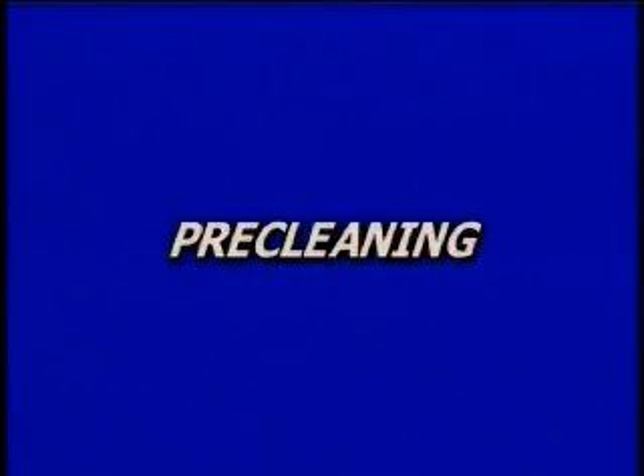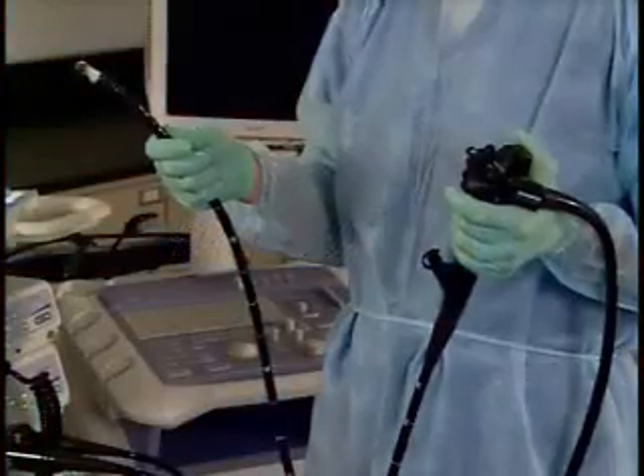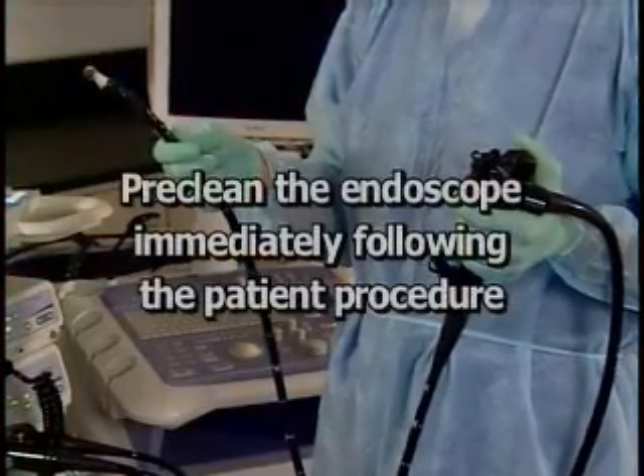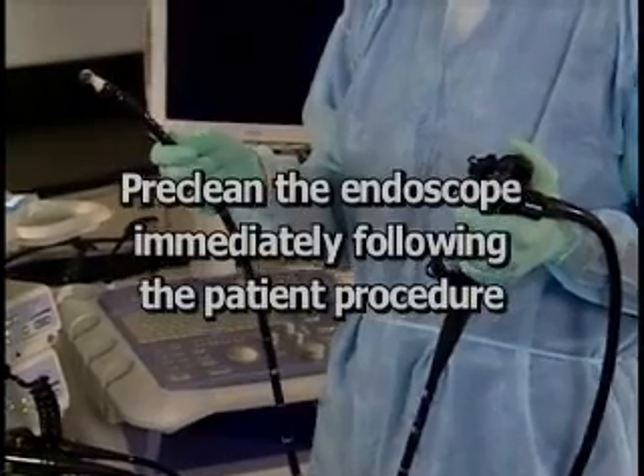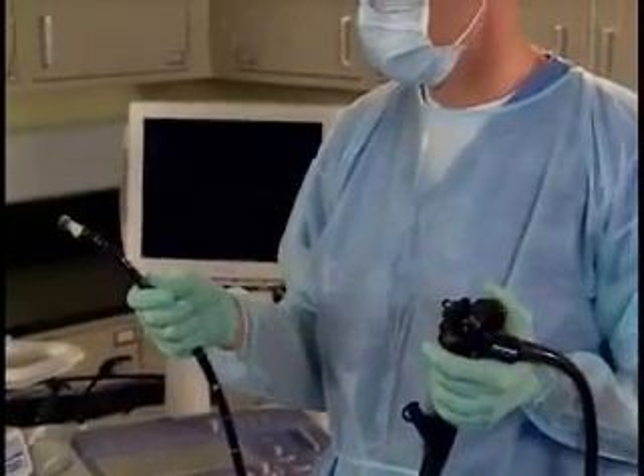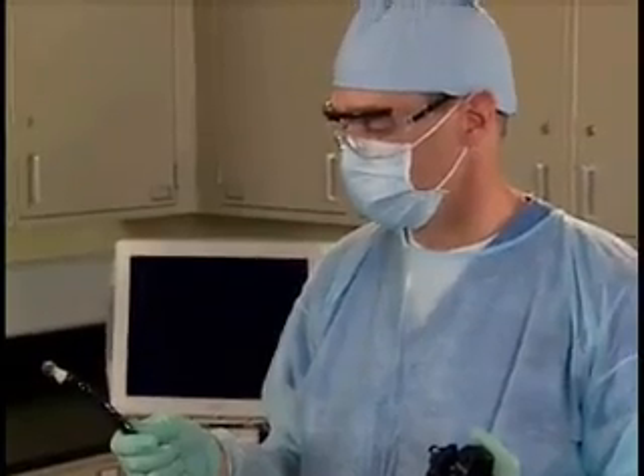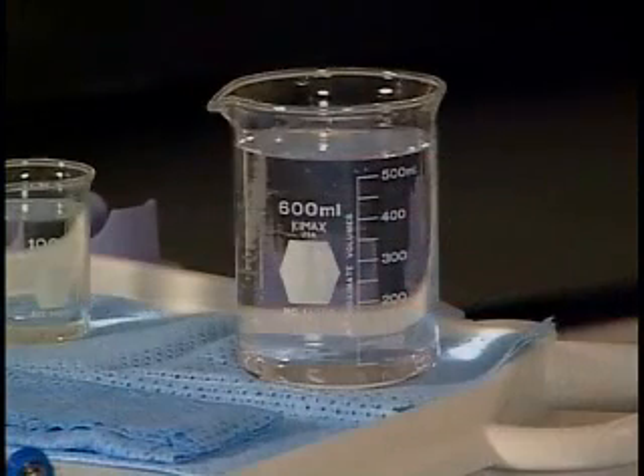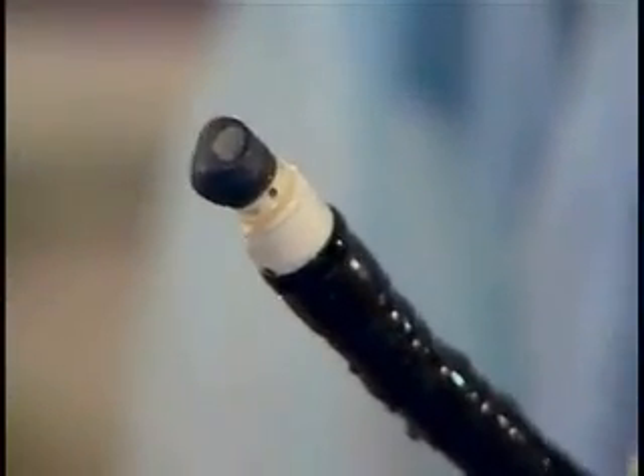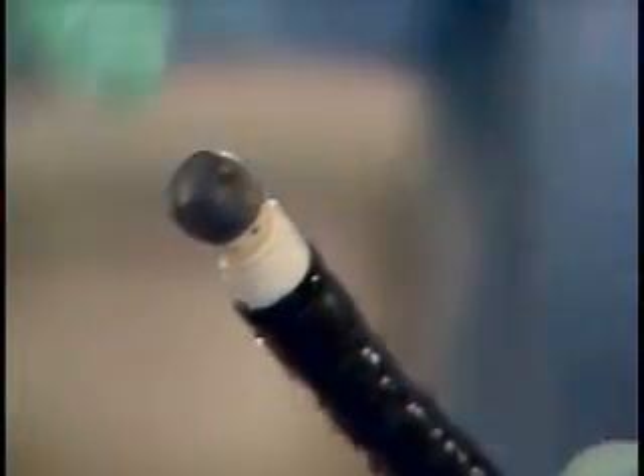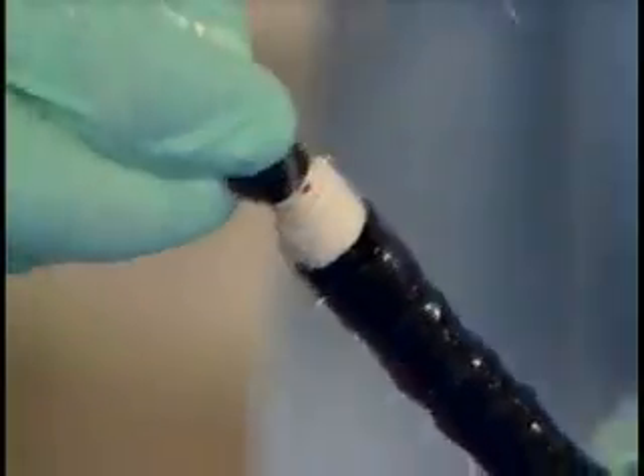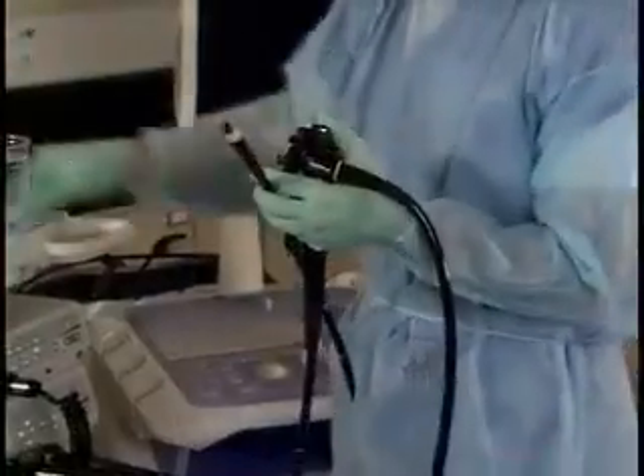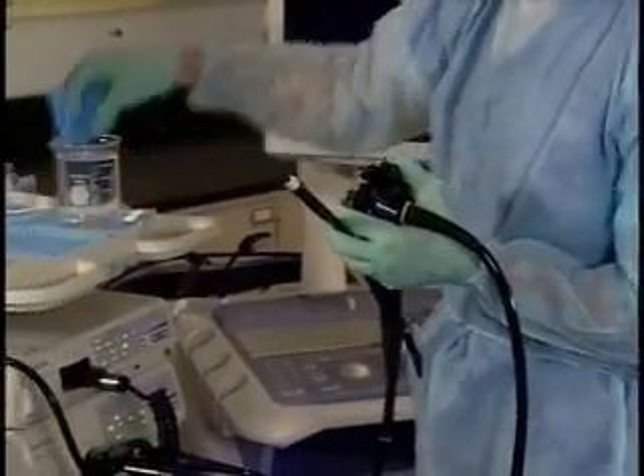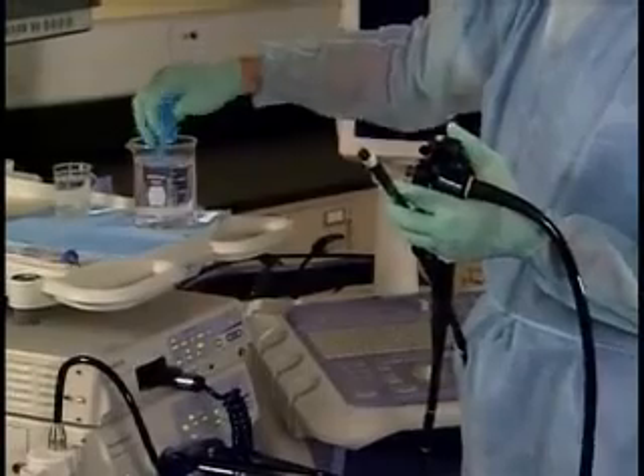Pre-cleaning is the first reprocessing step and is performed at the bedside immediately after the patient procedure. Pre-cleaning is critical to remove gross patient debris from the endoscope before it has a chance to dry. You will need a 500 milliliter container of detergent solution nearby. Remove the balloon, if attached, by slightly inflating and then lifting up the rear band of the balloon. Discard the detached balloon. It is a single-use device.